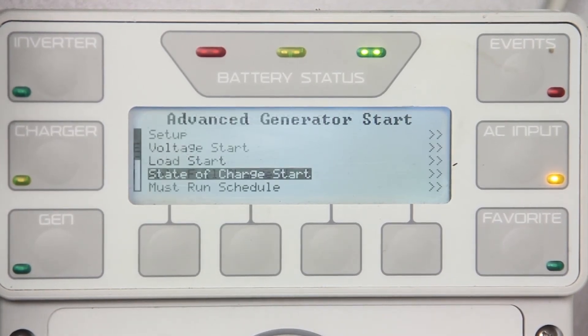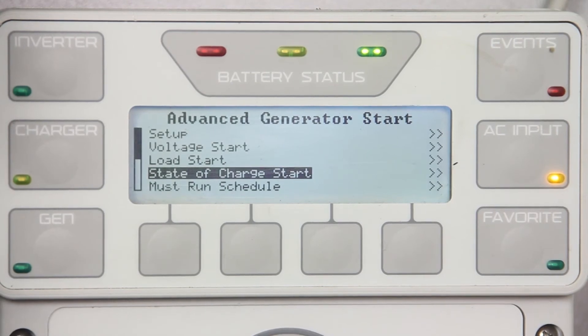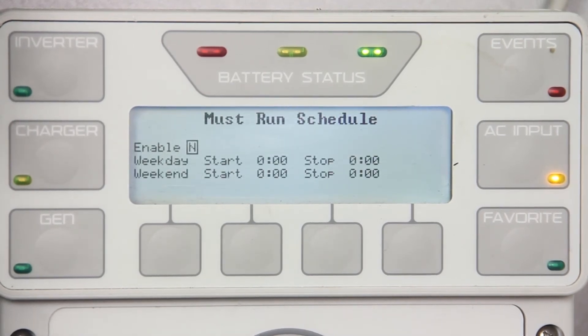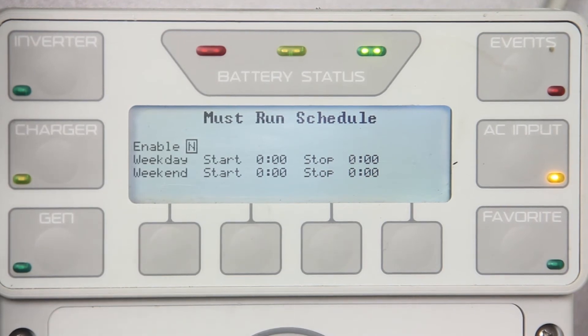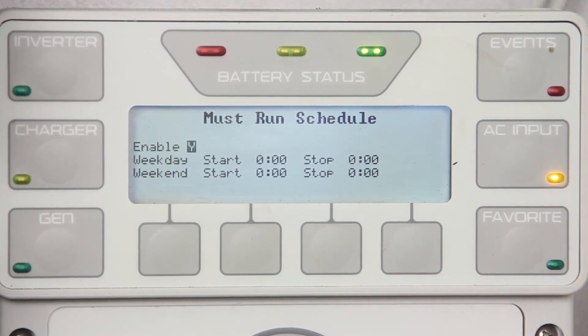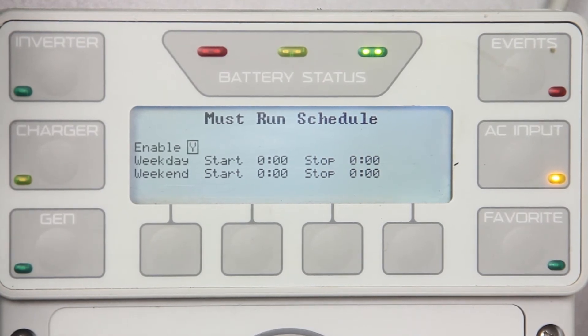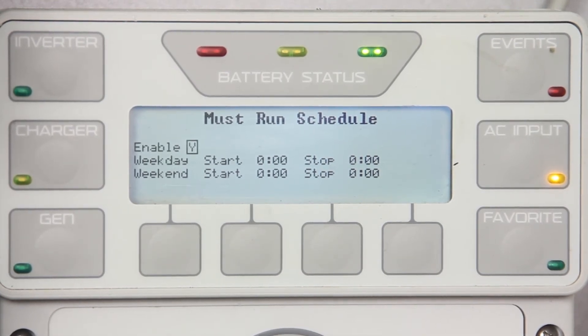Press up once and scroll down to must run schedule. Must run schedule time is the daily period when AGS commands the generator to run. This is usually set because large loads are expected to be present. To enable, change the N to Y and enter the desired start/stop time.